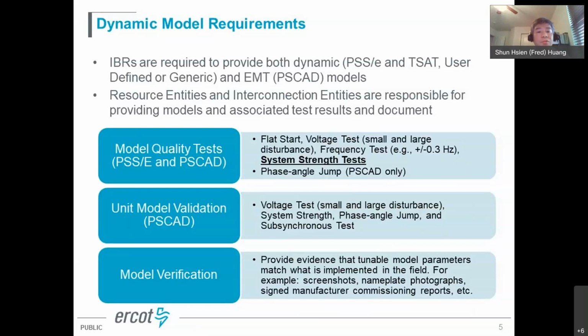The purpose is to ensure the model works properly and provides an adequate response in software like PSS/E and PSCAD. Typical testing includes the flat start test, meaning the model can be initialized without a fault for a period of time, along with voltage tests such as a small voltage step change or large disturbance like voltage ride-through, and similarly frequency tests such as plus or minus frequency deviation to see the model's response.